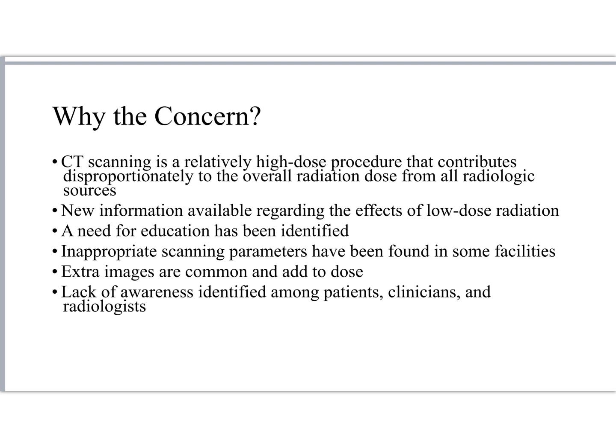Oftentimes there are some really great cases, not great, but scary cases you can look up, like Cedars-Sinai, brain perfusion at Cedars-Sinai, the case of Raven Knickerbocker, which we'll look at here for an activity in this class, where inappropriate scanning parameters were found. There have been examples of manufacturers who produce CT scanners that had some base level operating parameters for the scanners they shipped out with, and the technologists weren't aware of it because they missed the training, or maybe the training didn't even happen.